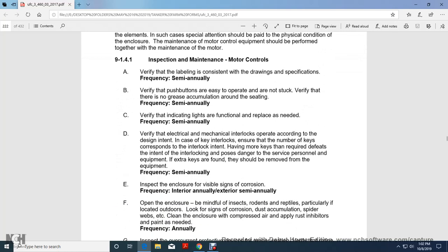Inspection of motor controls. Verify the labels are consistent with the drawings and specifications, semi-annually. Verify the operation of the operators and that they are not stuck. Verify there is no grease accumulation around the seating. Verify indication lights are functional and replace as needed, semi-annually.